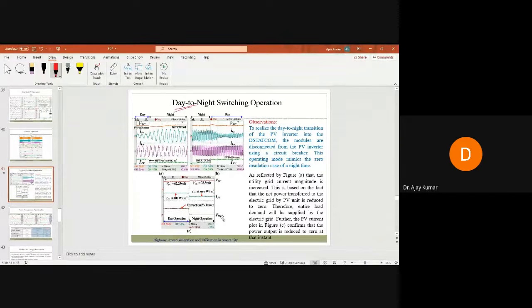Day-night switching means suddenly switching off the solar photovoltaic system. See, IPV is coming and 400 watt per meter square is incorporated, and then suddenly we switch off the solar photovoltaic system. Immediately the source current increases, because the load has to be supplied by the grid only. Similarly, if we suddenly switch on the solar photovoltaic system again, the source current reduces, and the DC-link voltage is always maintained constant. So this way, during day-night switching, this control algorithm works perfectly fine.